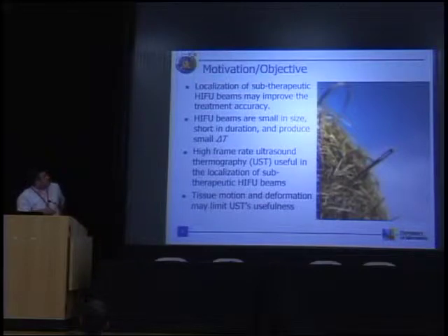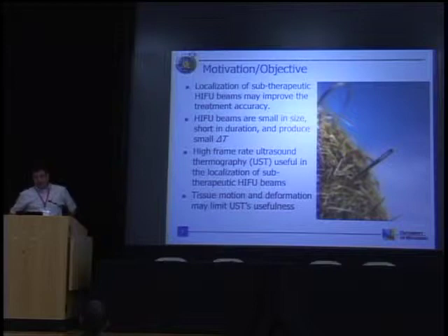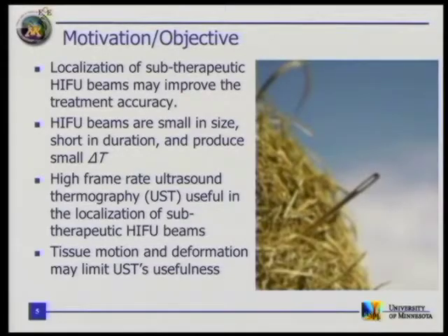So that's the challenge, and that's the kind of thing that MR, for example, will not do. This is not against MR. As I was talking to some of my colleagues here, MR is great for certain things, but this particular application of HIFU really requires ultrasound temperature imaging. And today we'll share some of our in vivo data that demonstrates that this is doable with ultrasound. So again, the characteristics of a HIFU beam is that small size, but also short duration.